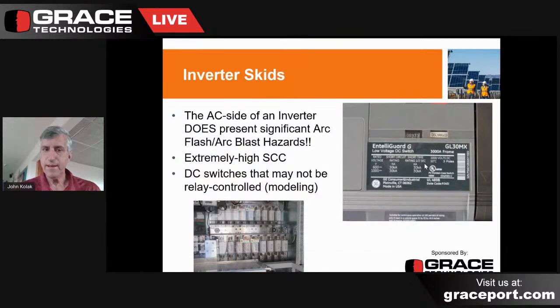Now, inverter skids, an interesting piece of equipment that requires some thought on both the arc flash and the training aspects. So first of all, the AC side of the inverter does absolutely present significant arc flash hazards. The AC side of that can have hundreds of calories of exposure and very significant short circuit current, very high fault current. So the AC side of the inverter does act like every other piece of AC system equipment that you've modeled in the past. It just is essentially a pad mount transformer and some conductors going into some switches, and we'll talk about that in a moment. Because you have this extremely high short circuit current, we talked earlier again about equipment duty. Well, that's absolutely in play on the AC side of the inverters, and any breakers or switches that are used on that side of the equipment.